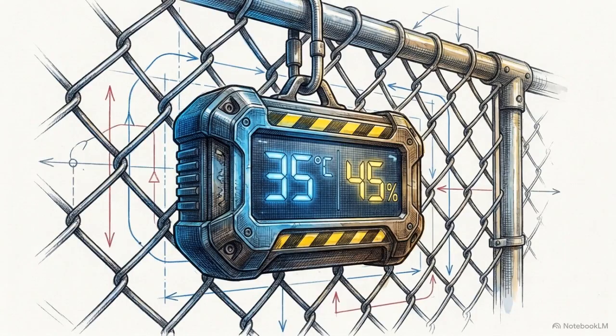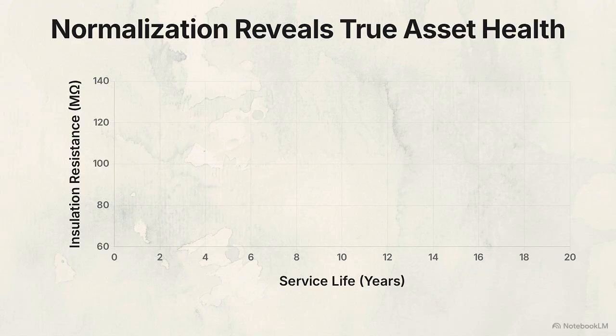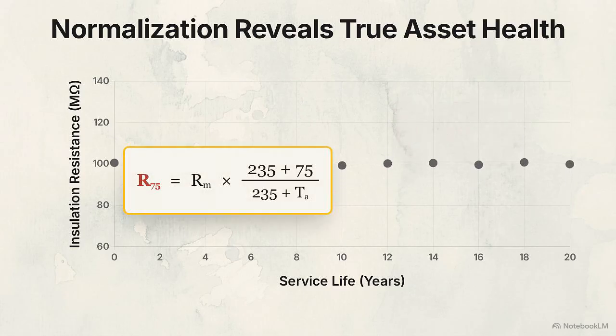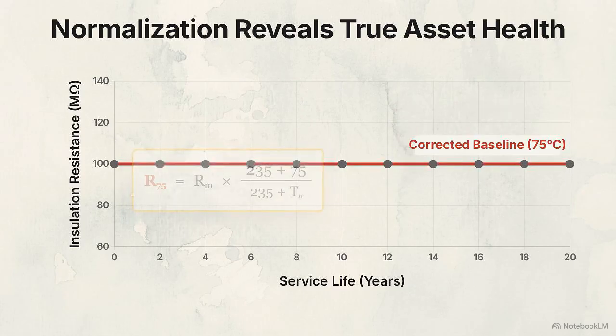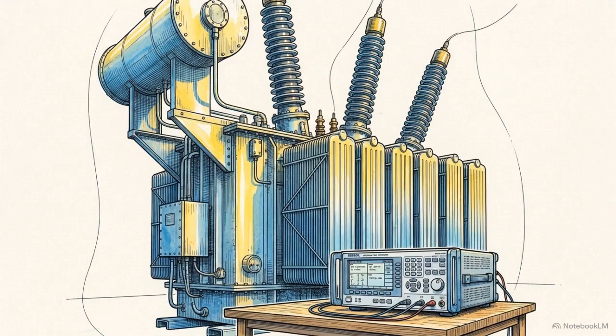Environmental factors are also captured. Ambient temperature and relative humidity directly impact insulation resistance, so these variables must be recorded to normalize the raw data for accurate longitudinal comparison over the transformer's lifespan. Ultimately, commissioning serves as both an engineering proof and a legal certification. It relies entirely on high-precision instrumentation and unyielding adherence to international standards.